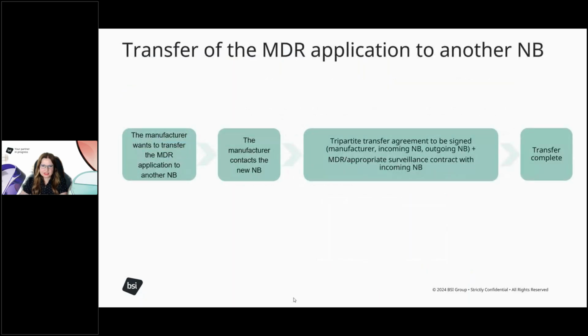So how can the transfer happen? Really, in a quick way, if a manufacturer wants to transfer the MDR application, they need to contact the new notified body. So there will be the need to sign off a transfer agreement between the manufacturer, potentially the outgoing notified body, and the incoming notified body. And there will be also some contracts to be signed off with the incoming notified body in order to cover the MDR conformity assessment activities and the appropriate surveillance for the legacy devices. And then the transfer is complete.